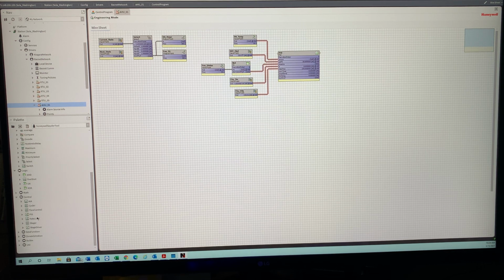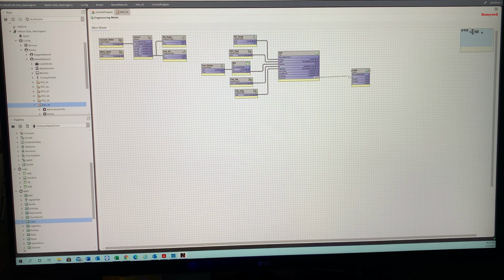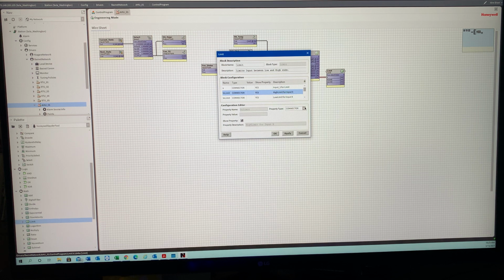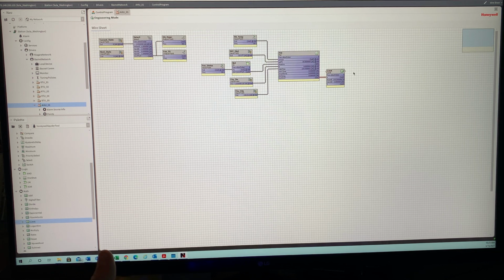So what we do is we'll put in what's called a limit block, which also helps out. We'll take our output here and put it in the X. Then we're going to go to configure properties. I'll bring this over here. Our high limit, let's make it a constant. Make it 100. Our low limit, we're going to make it 0. That way, when you have your output, you're doing 0 to 10, 2 to 10, whatever you like. This is the easiest way to do it to maintain that consistency.